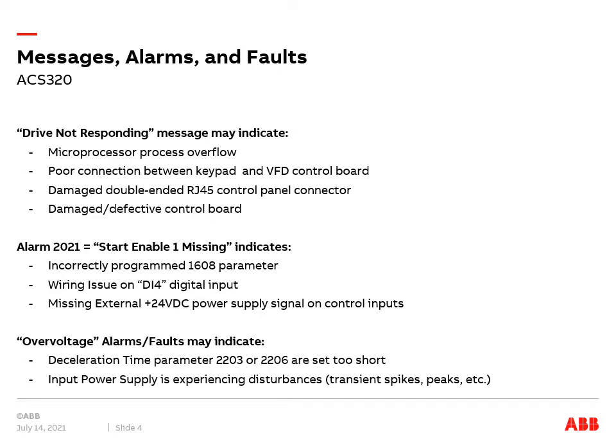Alarm 2021, start enable 1 missing, is triggered when a control input should be wired to digital input 4, but it is not. From the factory, the drive will want a control input on DI4, due to parameter 1608 defaulting to a value of DI4.